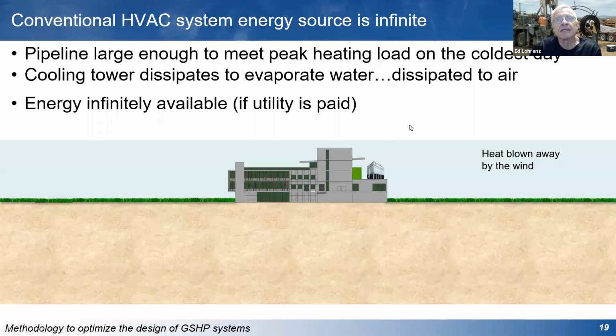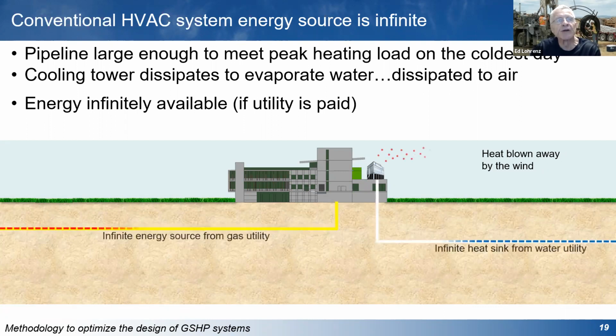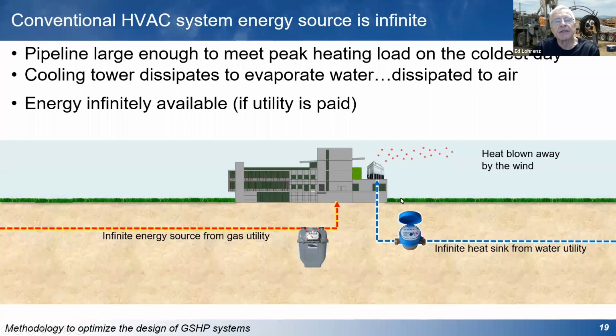So basically, there's a fundamental difference between designing an HVAC system for a conventional system and designing a system for a ground source system. With a conventional system, you're typically connected up to an infinite energy source, connected to a gas line, for example, or connected to a way of getting rid of excess heat from the building when you're cooling. Basically, dump it to the atmosphere and it blows away with the wind. And you're using a bit of water from the utility to help get rid of it.